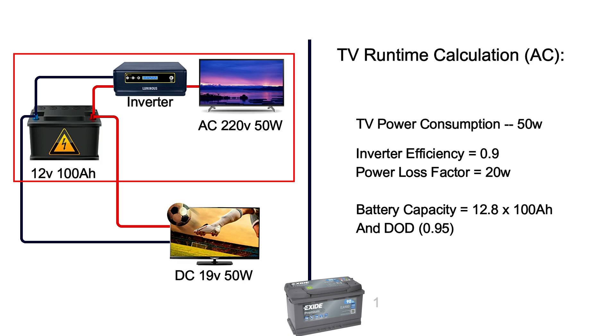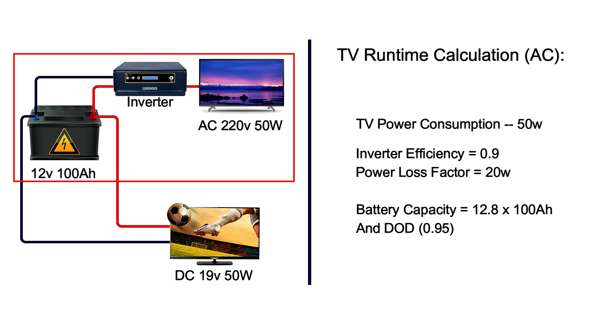If your battery is a lead-acid type, keep in mind that you can only get 50 percent depth of discharge, or a 0.5 discharge ratio — thus a 100 ampere-hour battery effectively becomes a 50 ampere-hour battery. Now that we have all the details we need, let's calculate the runtime.